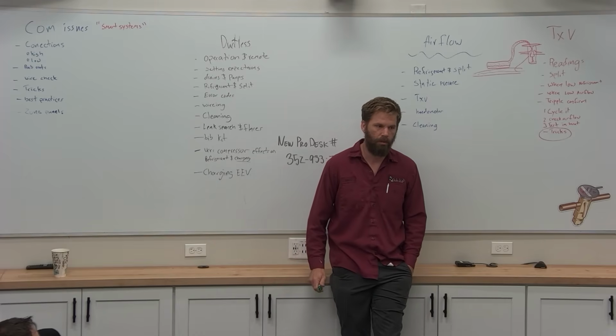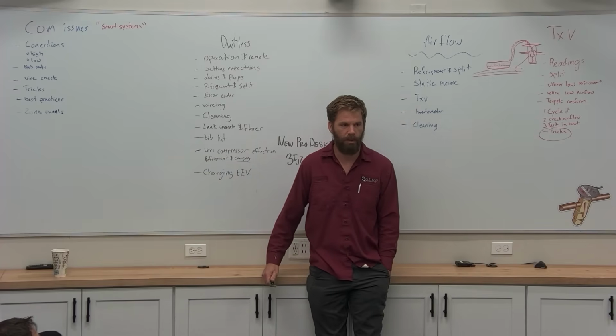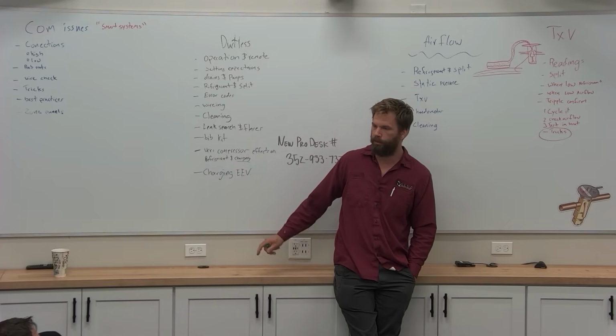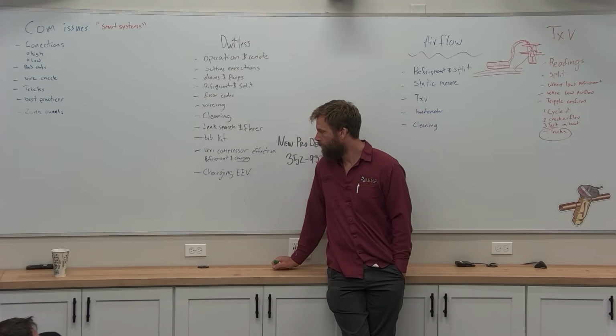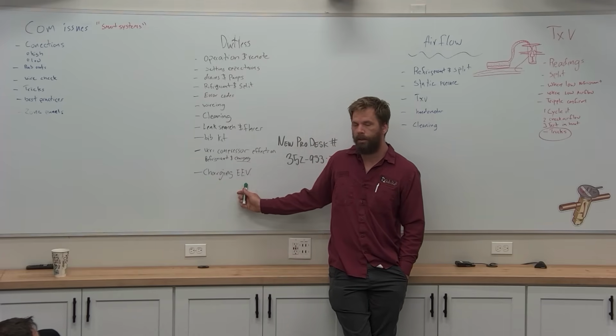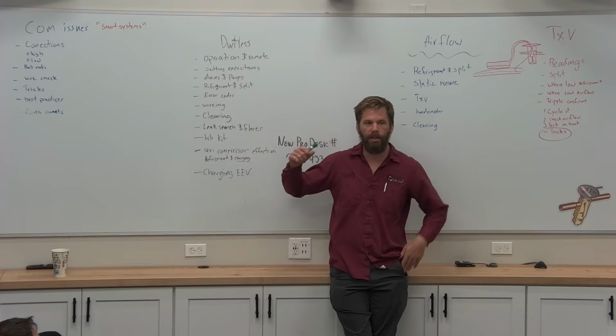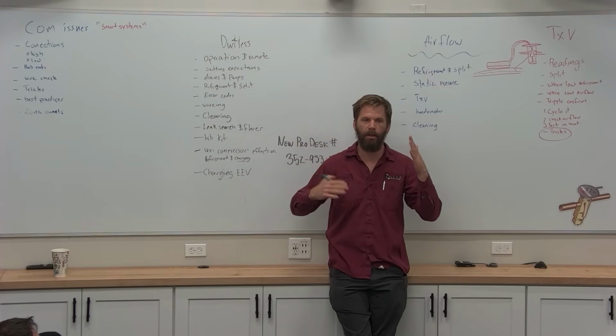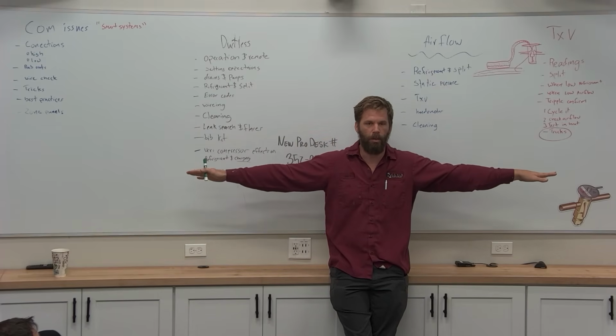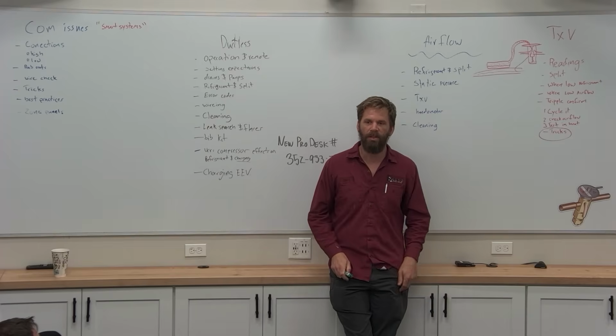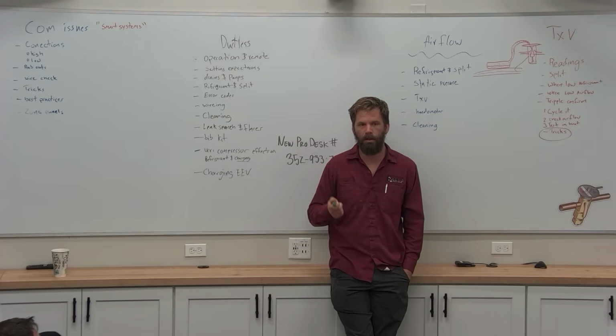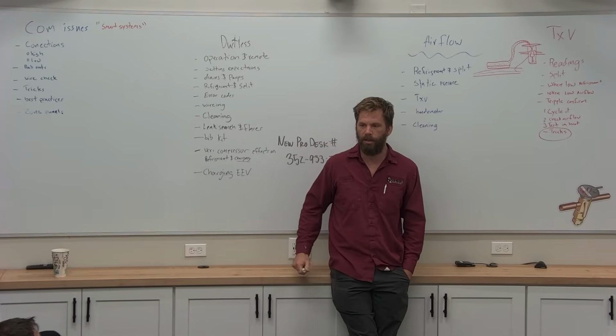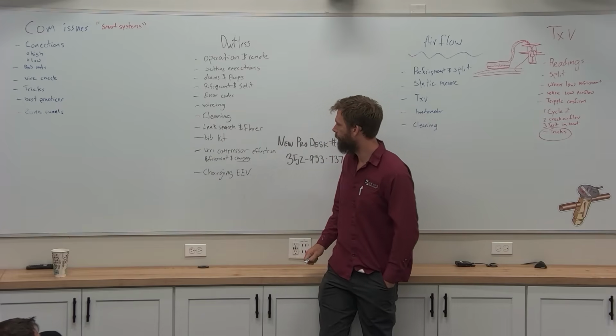Typically, you almost never run into it above 9 degrees if everything's perfect on the charge. So when you're adding, you add a little bit, the TXV starts adjusting, and you have to stop and let that settle, everything go back to normal, before you add a little bit more. So the process is much longer than you think it is. If you try to speed that up, it's very easy to overcharge this thing because the TXV is adjusting as you add. So there's your advice on that.